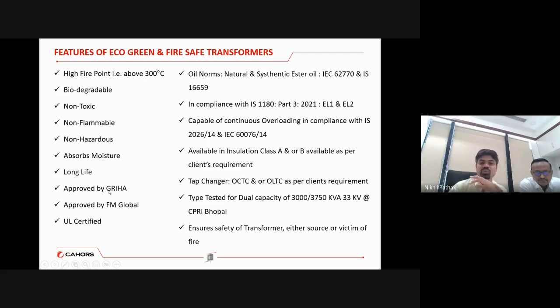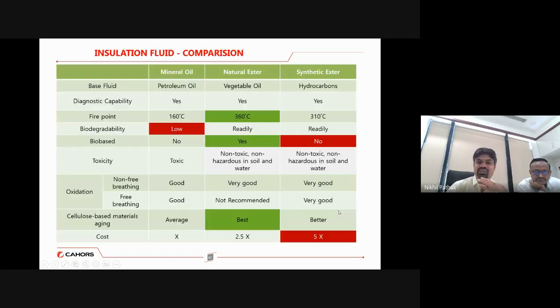So this ester oil is also approved by GRIHA and also approved by FM Global, which is an international agency for certifying hazardous and non-hazardous products, and it's also UL certified. So the oil is also complying with IEC standards and IS standards, and it is also complying with the BIS standard IS 1180 Part 3. So it offers continuous loading, and then it can be offered in class A or B. It can also be offered with off-circuit and OLTC configurations. So we have type tested the highest capacity of 3 by 3.7 MVA in CPRI itself. So it ensures the safety of transformers either as a source of fire or a victim of fire. So in both cases, this EcoGreen and fire-safe transformer is adopted.